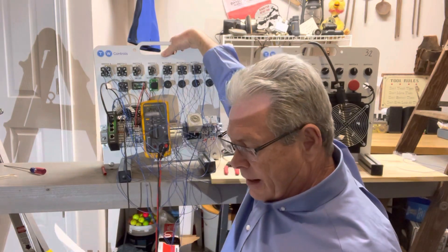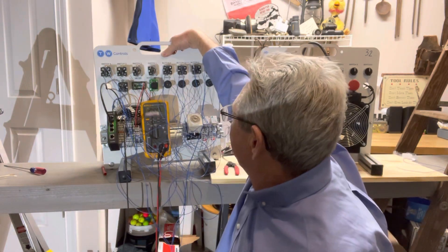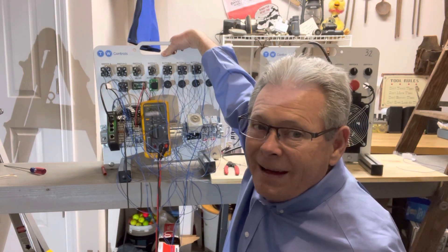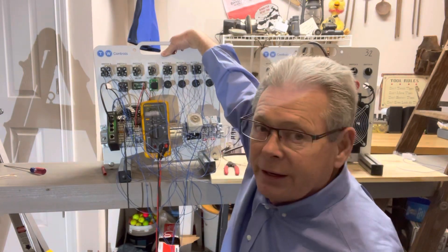Button 3, that's the amber light. The red light should read about 25 megaohms. I'm reading 24.5. That's pretty close. What else can it be, right?